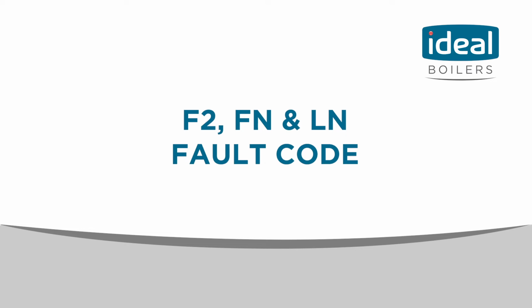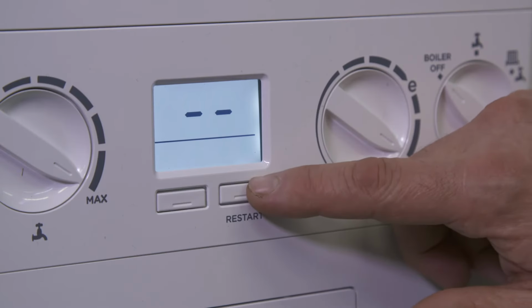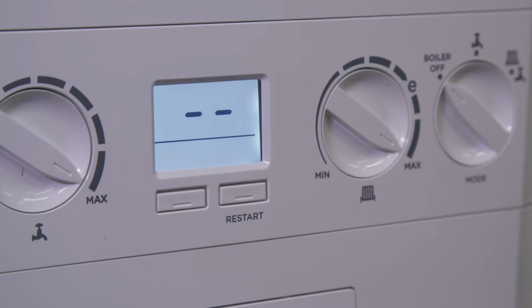If you do encounter an F2, FN or LN fault code, it indicates an ignition lockout. Check other gas appliances in the property. If the gas appliances are not working, go to your gas meter and make sure that the gas isolation valve is in the on position. Then try a restart. If the fault codes persist, contact Ideal Boilers.